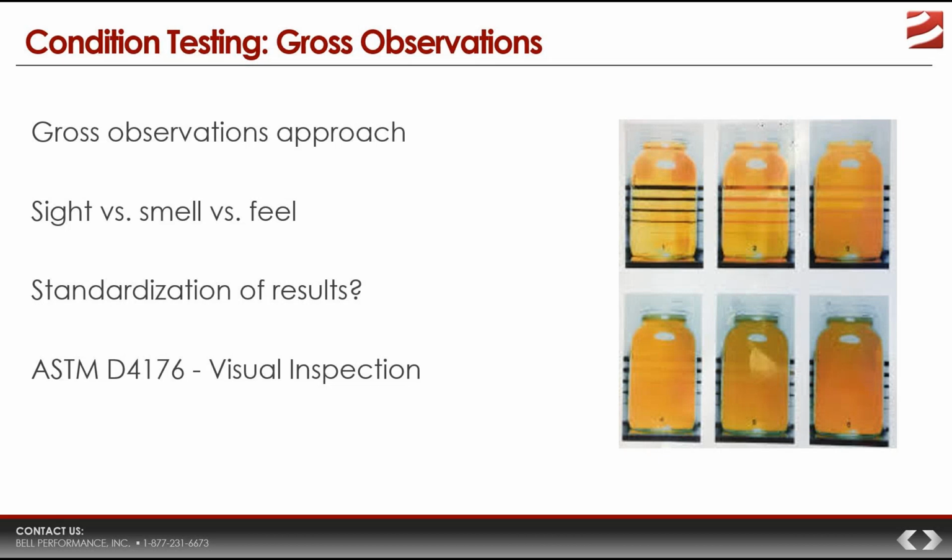Now, it has usefulness there because, if you think about it, pump dispensers at gas stations are supposed to have filtration systems that remove all of the particulate and the water because you do not want any of that reaching the end user. But this vortex test is not as useful if you're assessing bottom samples from a storage tank, because if you're pulling a three-phase bottom sample, then you're going to have water, free water, and particulate in it.